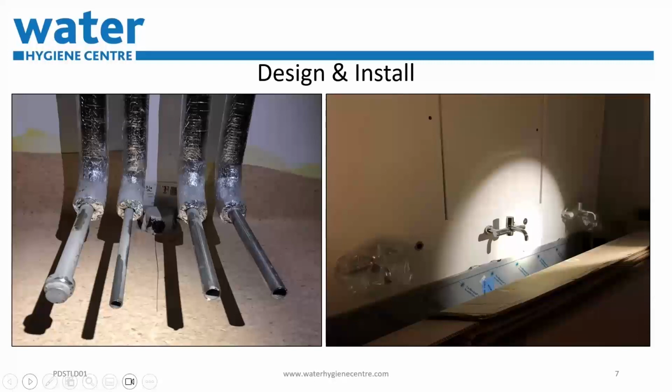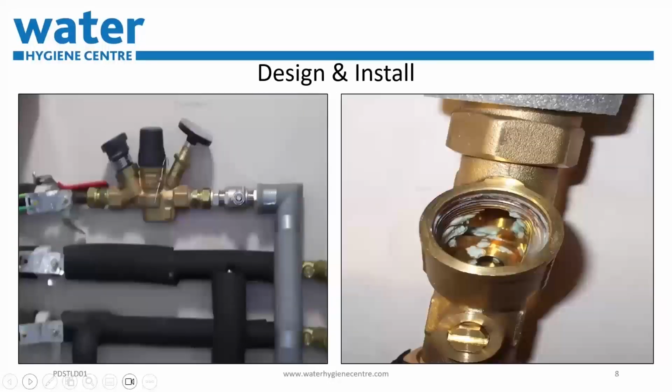And these are fixtures and fittings, pipework, valves, taps, TMVs. They should be kept free from debris and possible contamination through the delivery to site, storage on site, and installation. Open ends on pipework or components that are not kept sealed will invariably suffer ingress of debris and contamination. Okay, next slide, please.